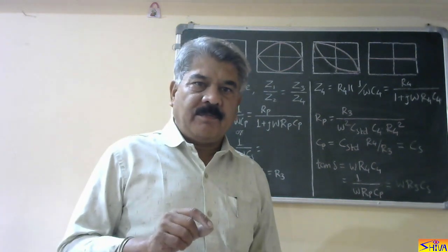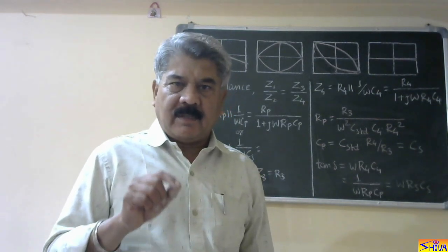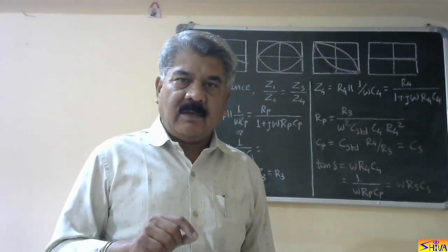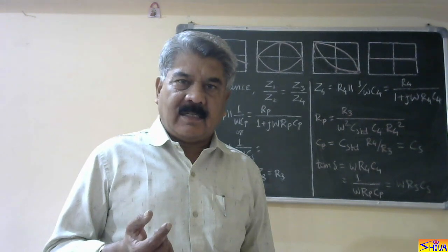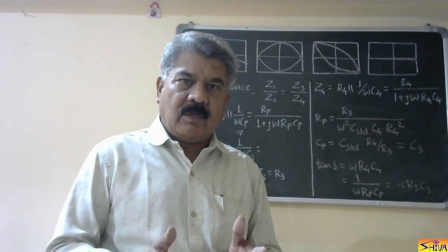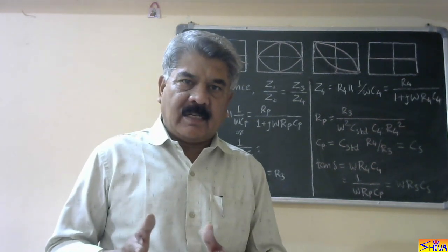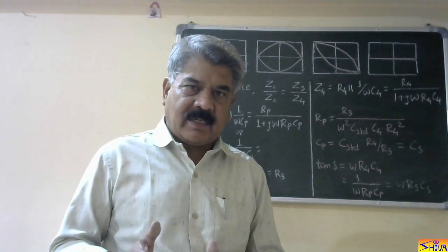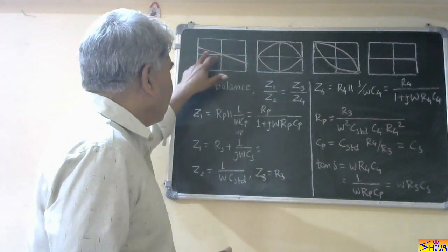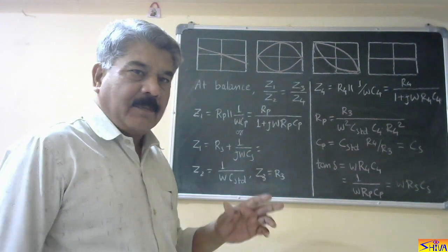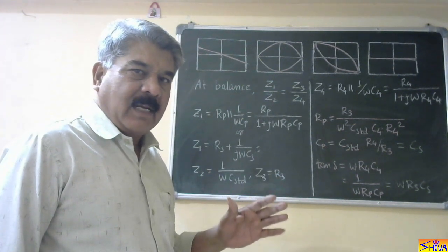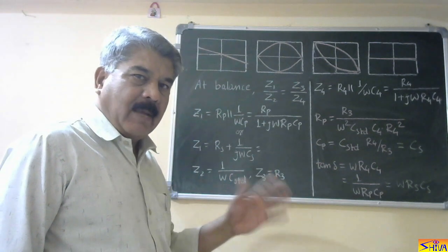because we are having a test specimen which is represented either by series combination of R and C or parallel combination of R and C. So if we find out the impedance, it will be having magnitude and phase angle. So if we get an inclined line, that represents phase angle is balanced, only magnitude imbalance is there.